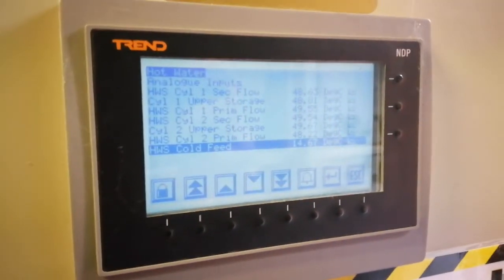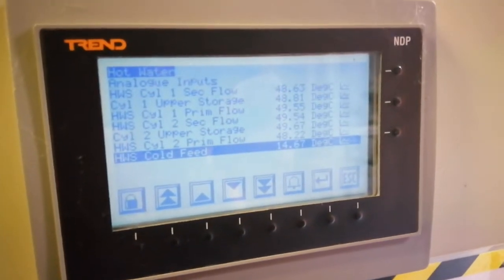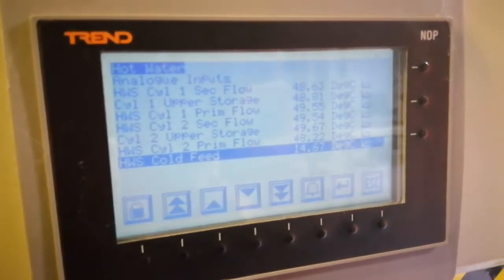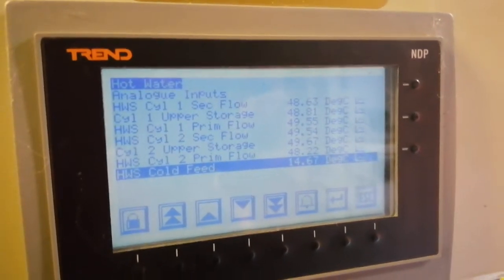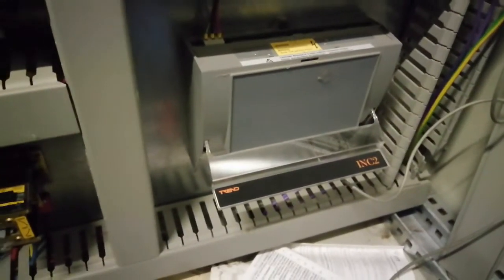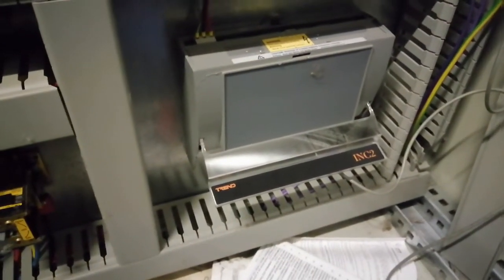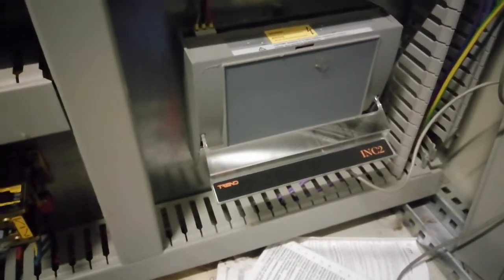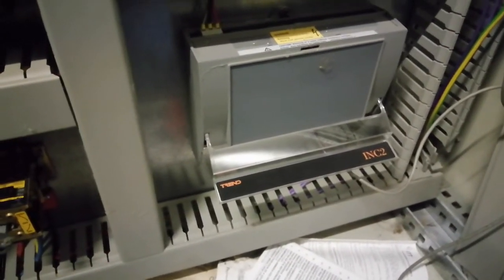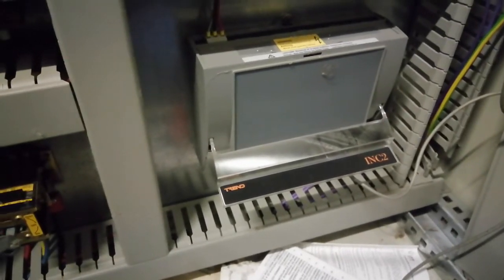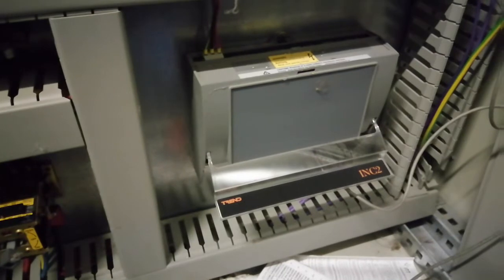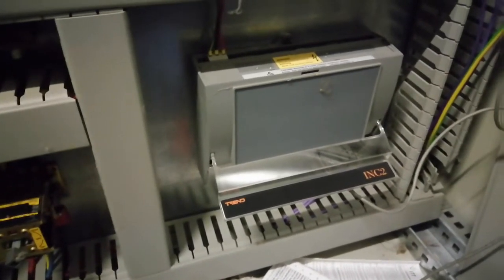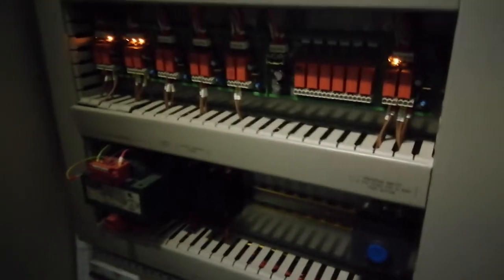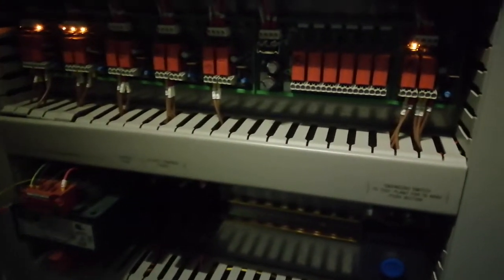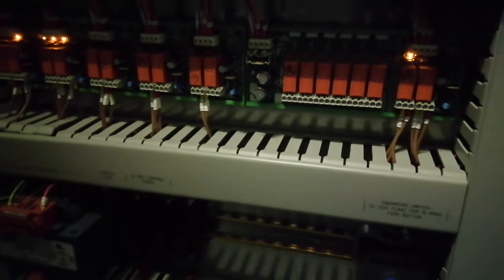Just going to show you how I got the temperature up from 42 Celsius on average on the cylinder temperatures to 49 Celsius. So down here we have this INC2. It's an internet work node controller. It's not working, and it's where it controls the times that the hot water comes on the boilers, the plate heat exchanger, and so on, what time it comes on from a main computer, but it's not working, so I had to bypass it. In another video I've shown you how to bypass the BMS. That's what I did in this situation. I had to move the jumpers along to bypass it.